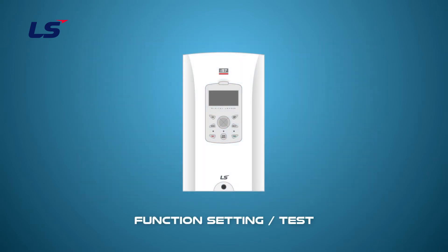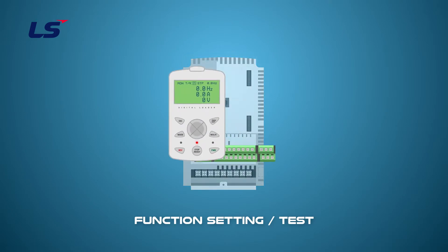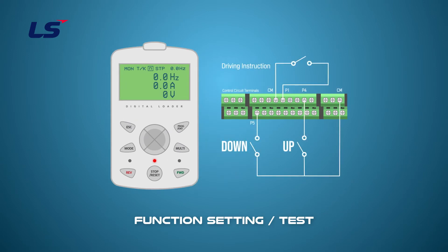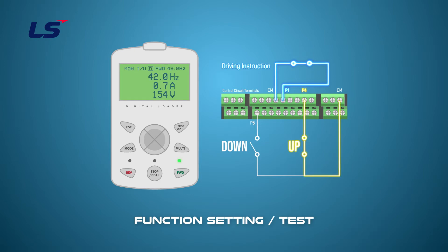When the multi-function digital input parameters are programmed to Up and Down, the frequency command source displayed at the top of the monitor mode changes to S. In this state, when the multi-function input programmed as Up is on, S changes to U to indicate Up operation and the output frequency increases. When the multi-function input programmed as Down is on, S changes to D.